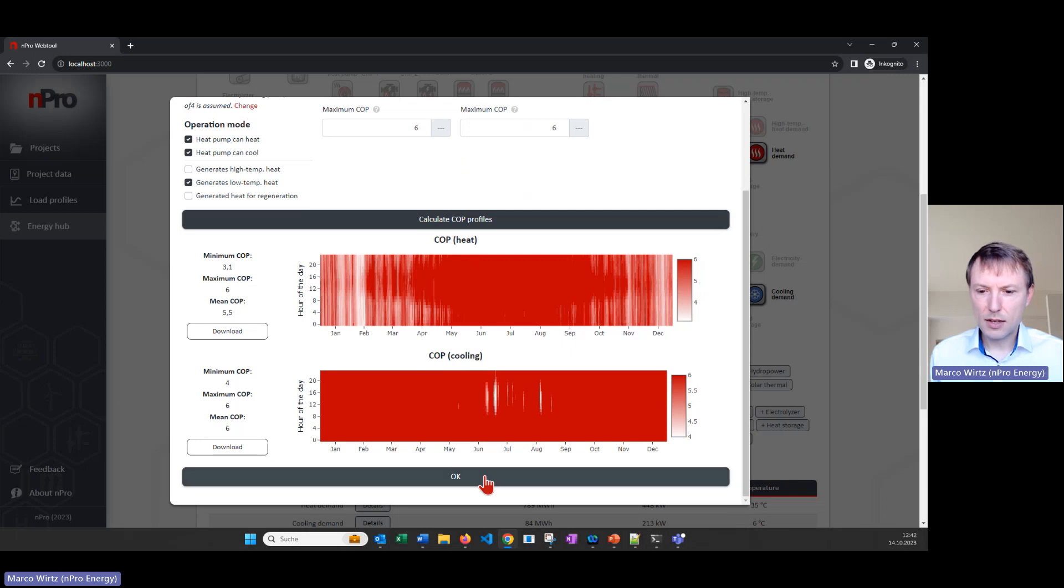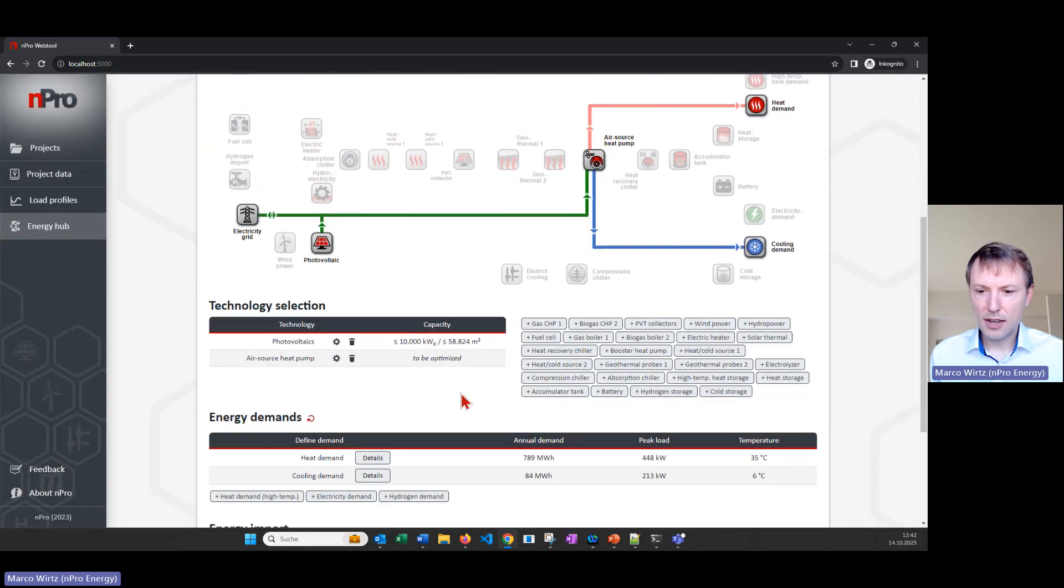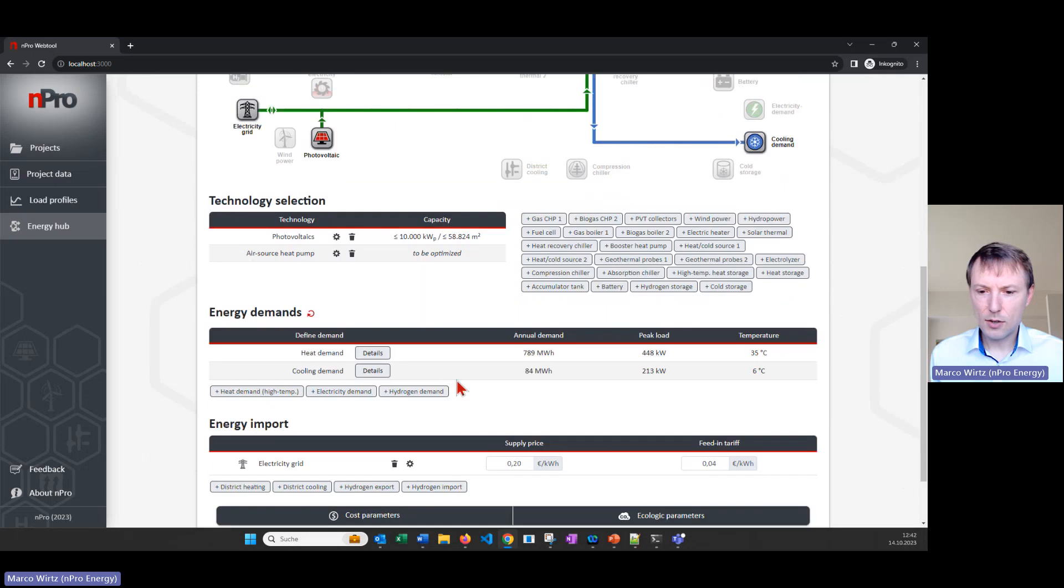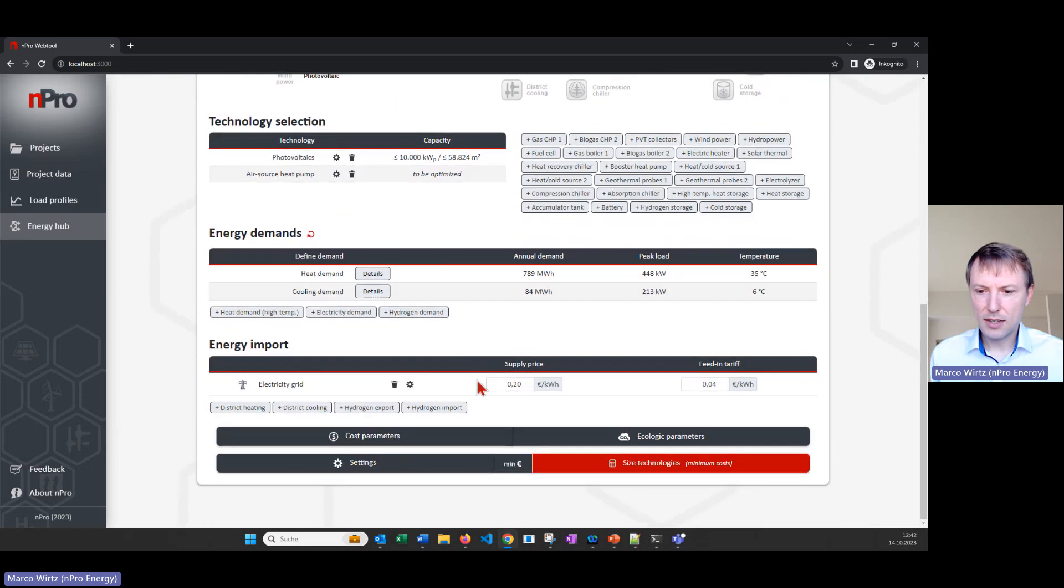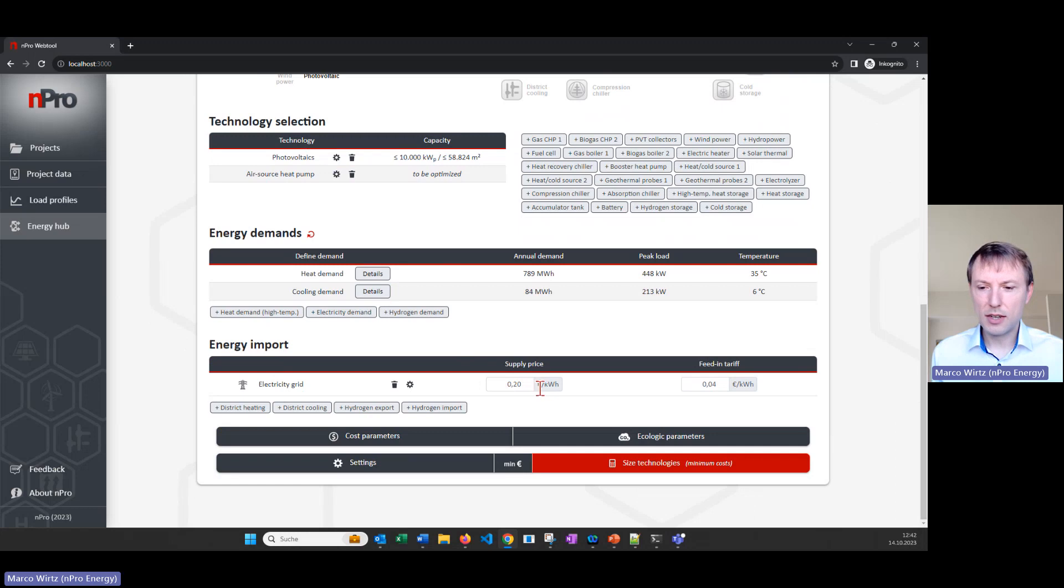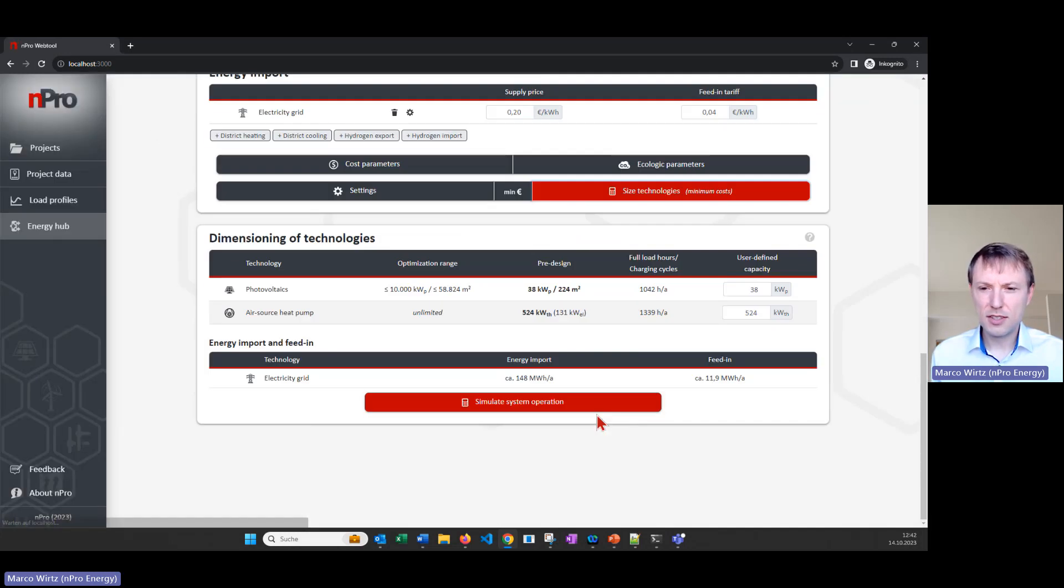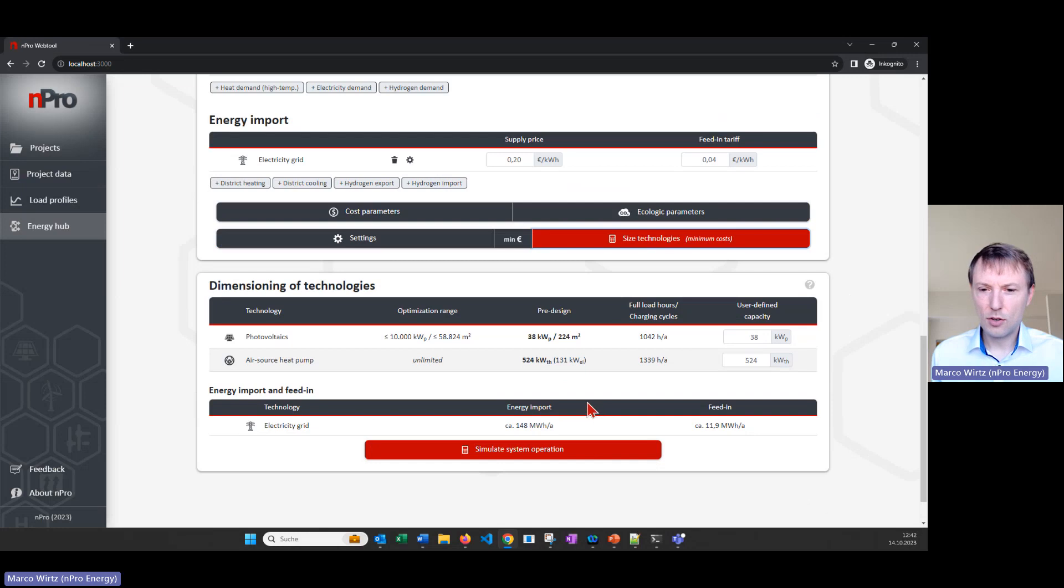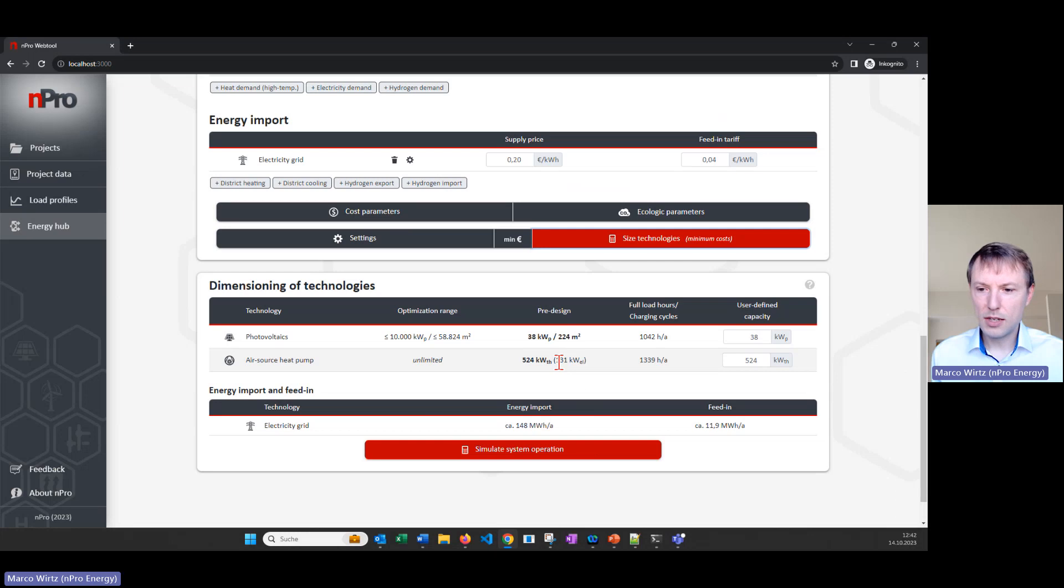Let's click on okay and then we can set the economic parameters of course like electricity price and so on. And then we hit the button size technologies. That's the first calculation step where we get the optimal dimensioning of the system. So how much PV is a good solution, how much air source heat pump do we need, what's the optimal capacity.